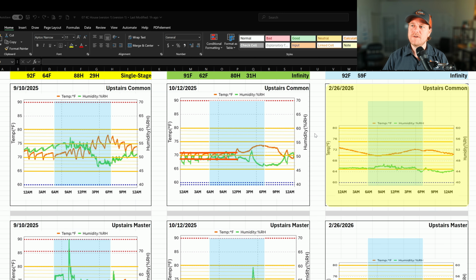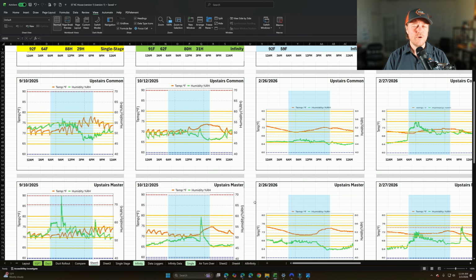And then if we look over here, it's just a straight line. And the best I can tell, since the system knows it doesn't have a big heat load, it's just slightly pumping the gas and then letting back off. And that's why we're ending up with almost no temperature swings. So please note that this is not a true apples to apples comparison. I won't be able to get that information for a couple more months. However, there are some key indicators that we can take away from this.